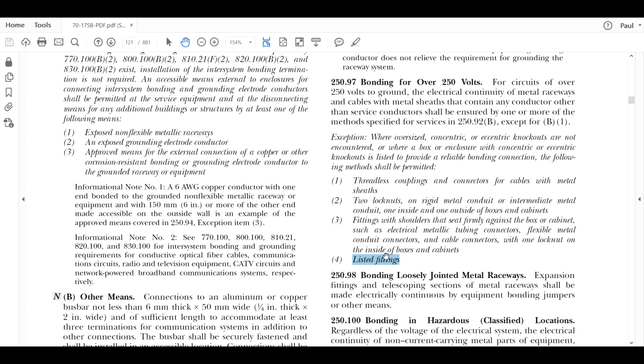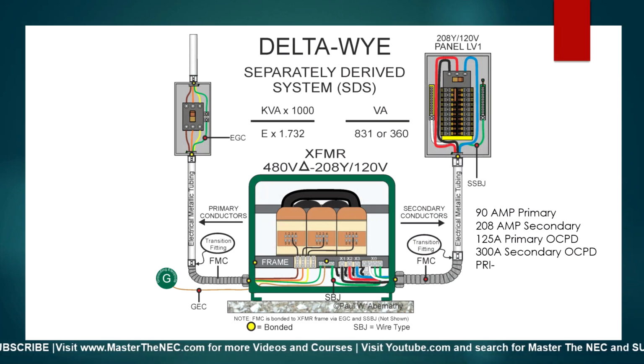So this is going to be all a really largely encompassing list right here. Okay. So that's how we're going to do it there. So bring it back to the PowerPoint. In reality, here, if I've got the equipment grounding conductor and I've got one of those accepted fittings that are listed in the 250.97 exception, because these conductors are over 250 to ground, then I can get away with just a simple fitting and a simple connector. Remember, I'm not worried about the lock nut limitation because I'm not going to 250.92(B), because I'm using the exception in 250.97.